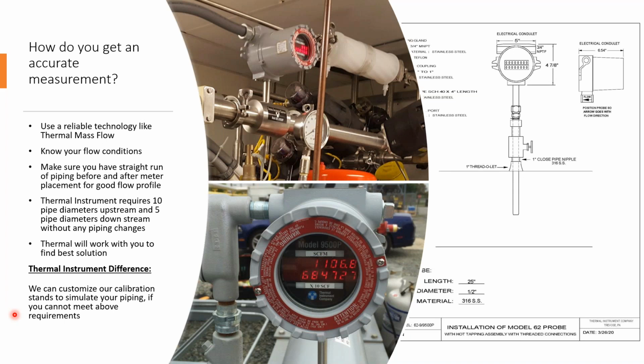So now let's get into what you need to know about getting an accurate measurement using thermal mass. First off, it's really important to know that you've got the right technology, because some technologies are better than others when it comes to measurement and what you're trying to measure. So it's definitely talking with your salesperson and then getting on the phone with us if need be. We can help make sure that we're giving you the right thing for the right application. It's also important to make sure that you know your conditions. Know what your temperature ranges are, know what your pressures are, know what your flow rates are, know where you need to measure down to, what you need to measure up to. Those are all good things.